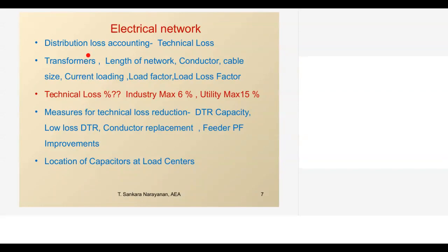This is on the distribution network. In the distribution network, the first challenge is how we are doing loss accounting. If we want to do a clear technical loss accounting, we have to cover losses in the transformer, total length of the network, conductor and cable size, and current loading. Up to these three activities we will be able to get data fast. When it comes to current loading, a large amount of data has to be collected. Then load factor and load loss factor can be considered for calculating.